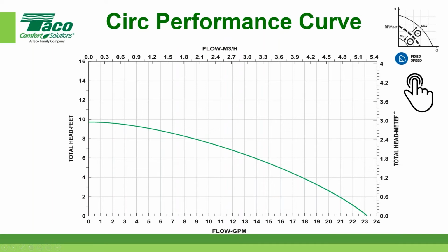I'm showing the icon here, and I'm telling you that it's a manual setting in this case. This is a good old 007, believe it or not. I think. Yeah, about just under 10 foot of head and about over 23 gallons a minute. But this would be fixed speed. It's got a maximum speed that it runs, a fixed speed that it runs at, and that's your circulator performance curve. Okay. Now, the reason I showed you that, I took you back to standard efficiency.